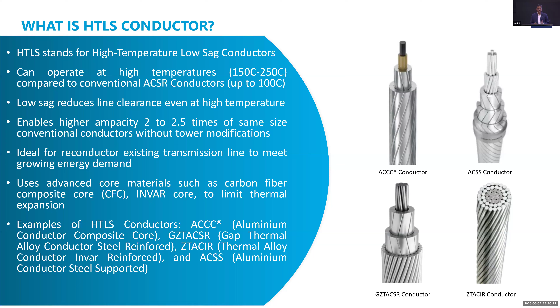For those of you who do not know what HTLS conductors are, it's a group of conductors which can operate at a very high temperature while maintaining the sag of traditional ACSR conductors. Traditional ACSR conductors have been around for the last 130 years and can operate up to about 100 degrees Celsius, but this HTLS group can operate up to 250 degrees Celsius.